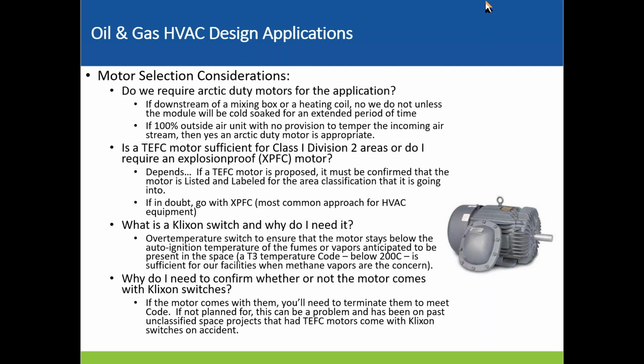A lot of these motors for hazardous areas will come with over temperature switches or Klixon switches. Really what they're doing is keeping your motor safe and at a T code, or temperature code, below the auto ignition temperature of whatever your hazard is. So with methane, we typically pick a T3 temperature code, keeping it below 200 degrees C.